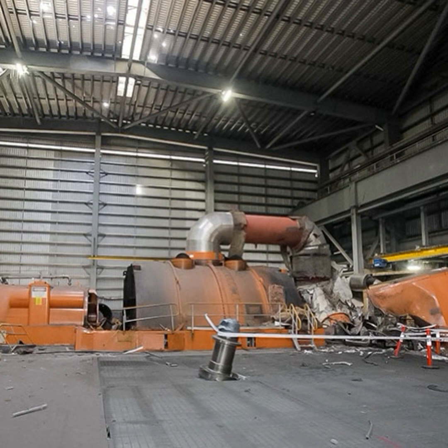Even though the local breakers were inoperable, at any time, the Callide substation breaker could have been opened. During the investigation, it was determined that AEMO and PowerLink were ready to isolate the Unit C4 from the grid as soon as CS Energy requested them to do so. However, the request was never made. There's a lot to unpick here, so let's start with what happened with the DC power system.